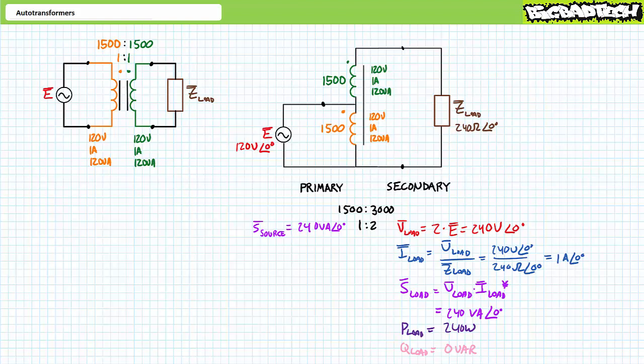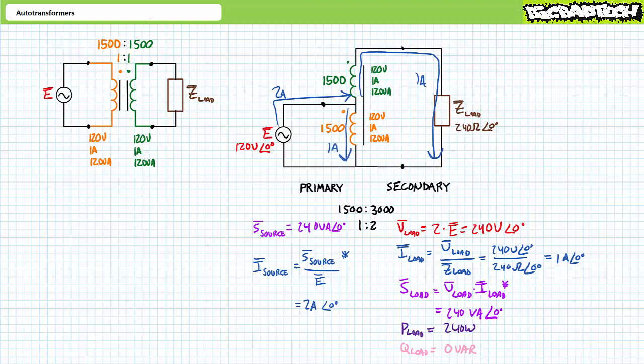Assuming the autotransformer is 100% efficient, we could say power in equals power out, such that the primary input must also supply 240 volt amperes of apparent power. An algebraic manipulation of the power equation solved for current demonstrates the primary input side of the autotransformer draws 2 amps of current from the 120 volt source. An application of Kirchhoff's current law at the center tap demonstrates 2 amps of current enters and 1 amp travels through the load in a clockwise direction. This means 1 amp travels through the bottom winding top to bottom.